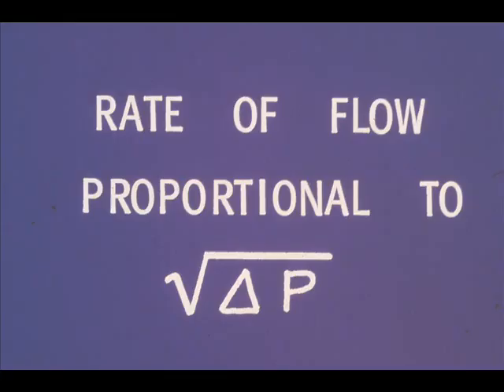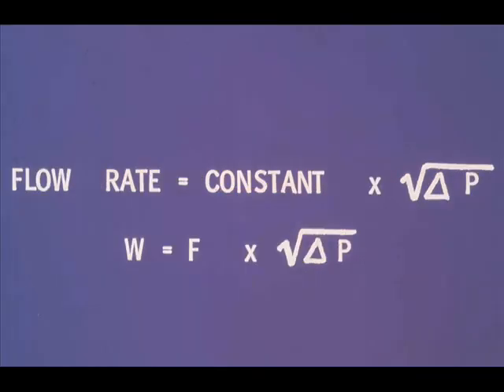We discussed pressure drop across an orifice, and that rate of flow was proportional to the square root of the pressure drop, or delta P. We talked about meter constants, and said that the flow rate for a particular orifice and meter installation could be determined by multiplying the meter constant by the square root of the delta P.